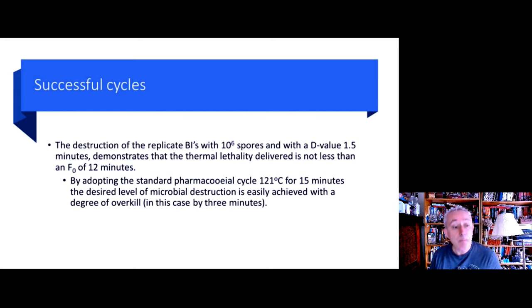So what makes a successful autoclave cycle? Well, we need to be able to demonstrate the destruction of the biological indicator, which we prove by subculturing it after it's been through the autoclave cycle. And we should be able to run a standard pharmaceutical cycle at 121 degrees for 15 minutes, and easily achieve the desired level of microbial destruction.